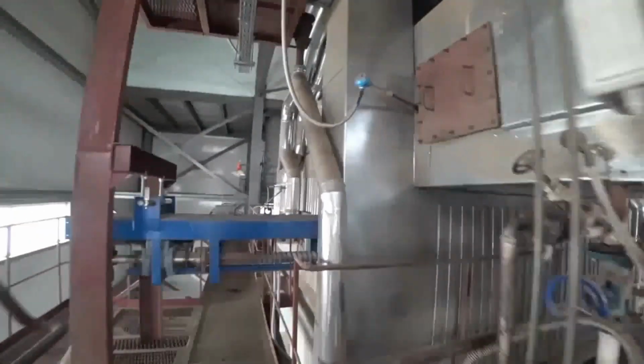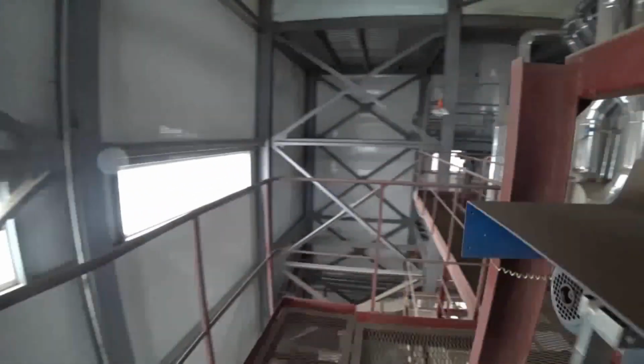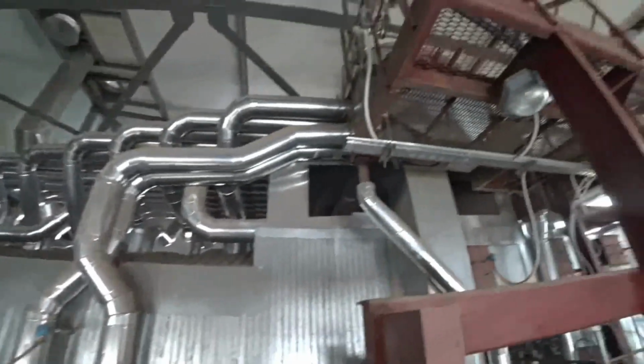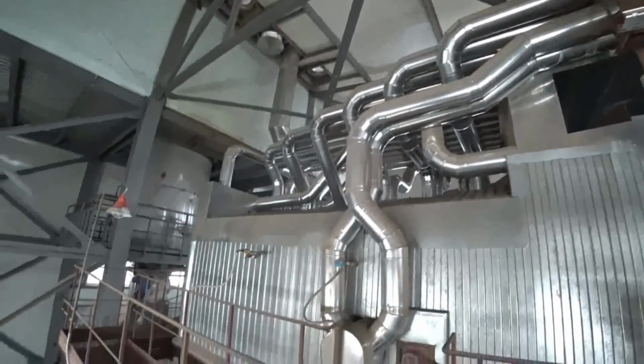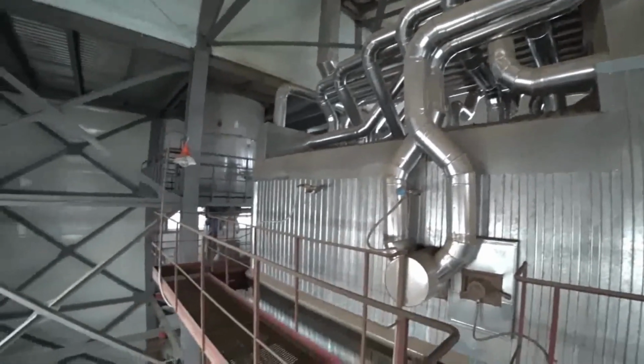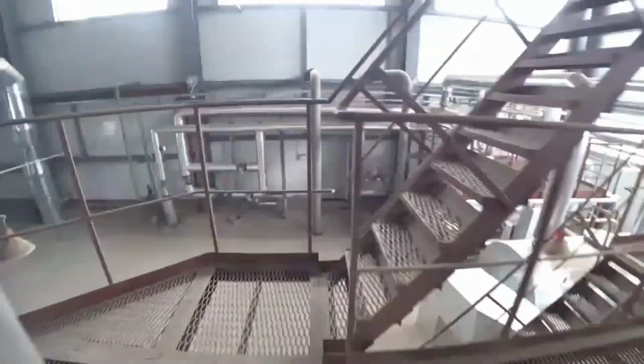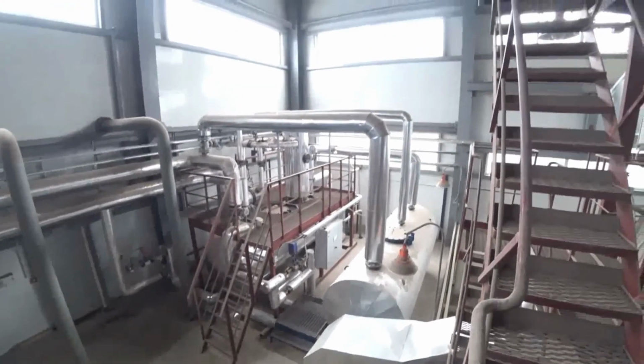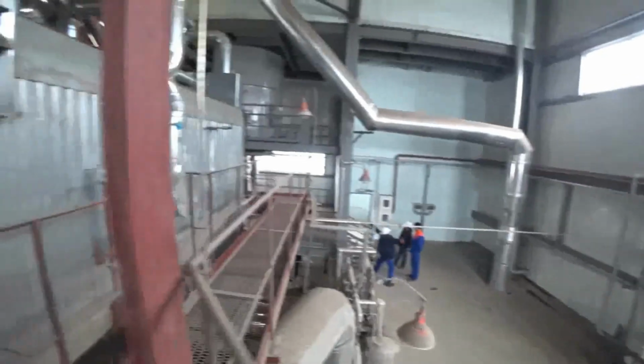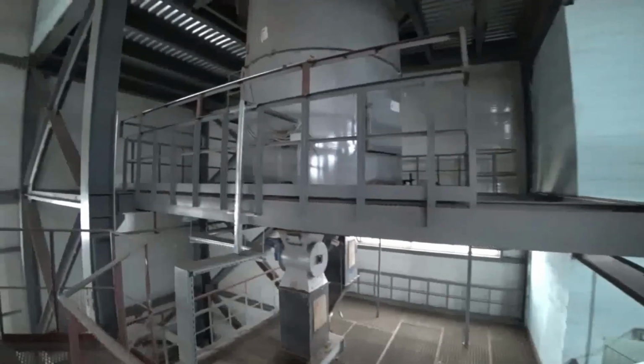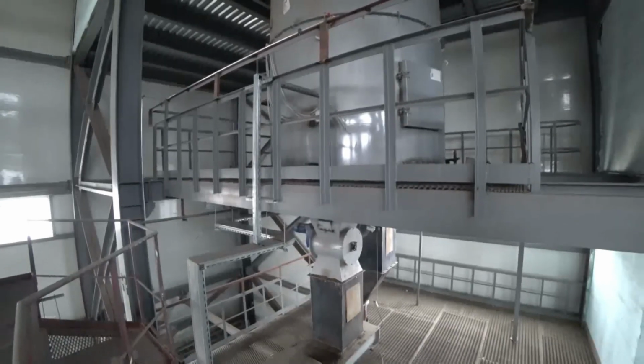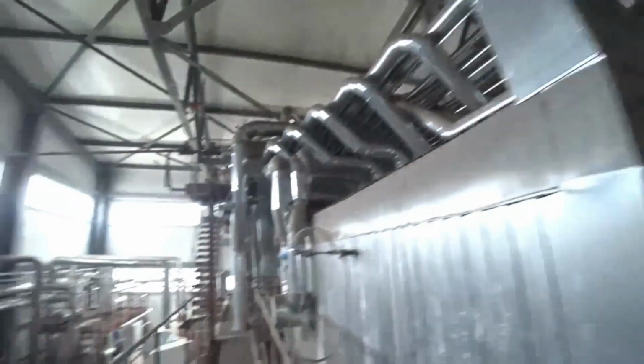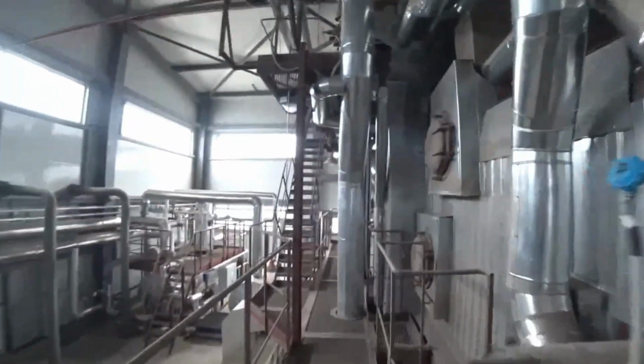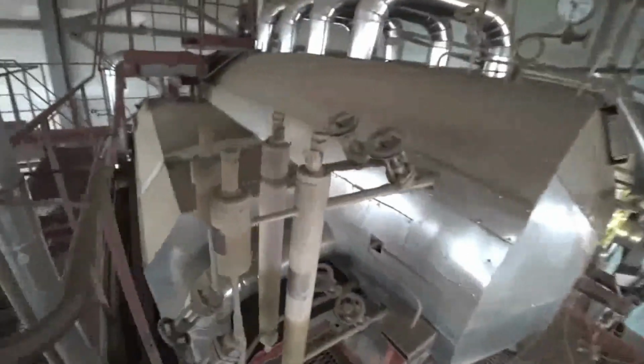Let's go further and meet more blowing devices on our way. All devices are included in a single boiler cleaning system. The system starts working 1 to 2 times a day when the temperature of the flue gases rises by 20 degrees above the nominal. The nominal temperature of the flue gases is 180 degrees. Here is a round agitator hopper designed to store fuel for 2 hours of boiler operation. Steam drum of the boiler.